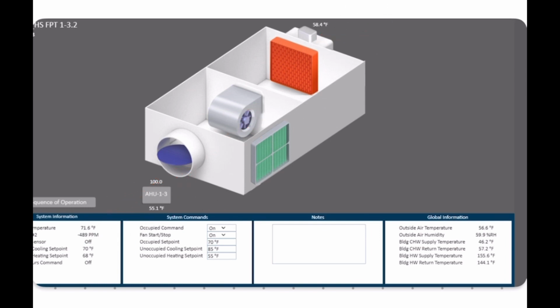Now, where are we getting that cooler from? We're gonna talk about that in a little bit, because your cooler, you get it from this air handler over here. In this case, it's 1-3, and that's how you get your cooler. And it tells you right there the supply cooler temperature that is coming from your air handler unit. In this case, it's 1-3. On this VAV box, you have to have your blower running at all times for cooling and heating. On some other VAV boxes, you don't need the blower.